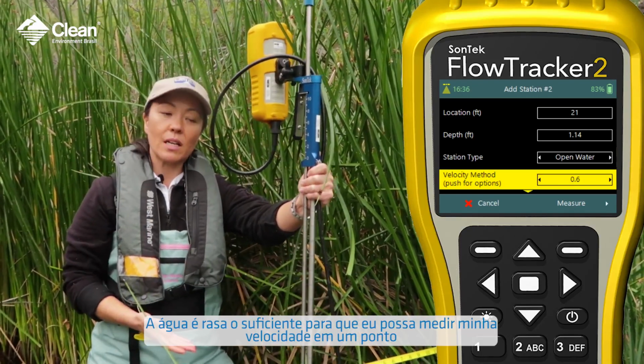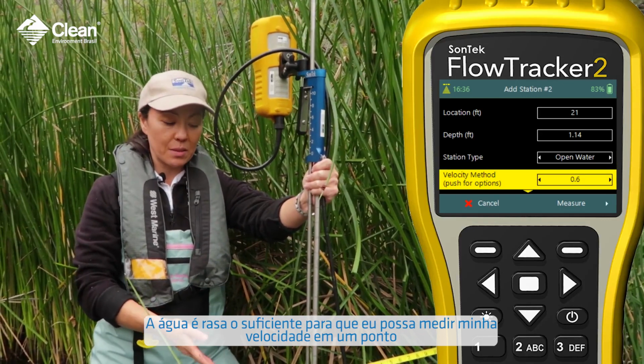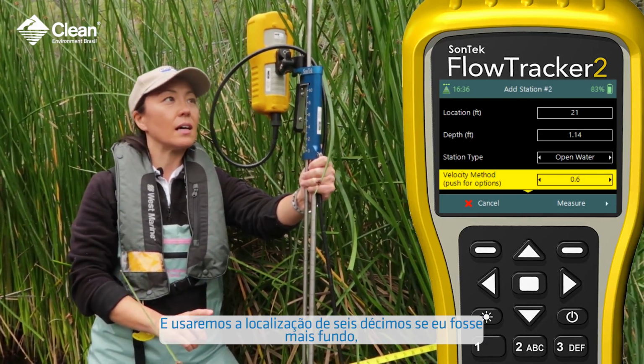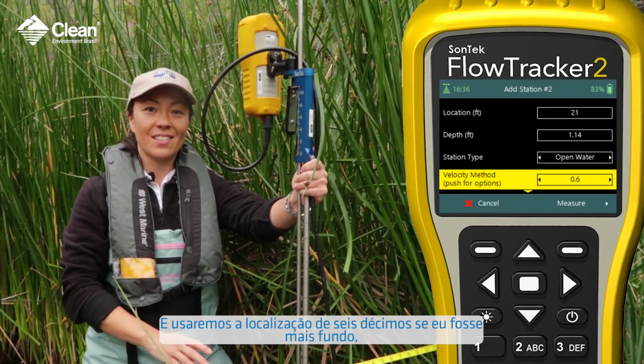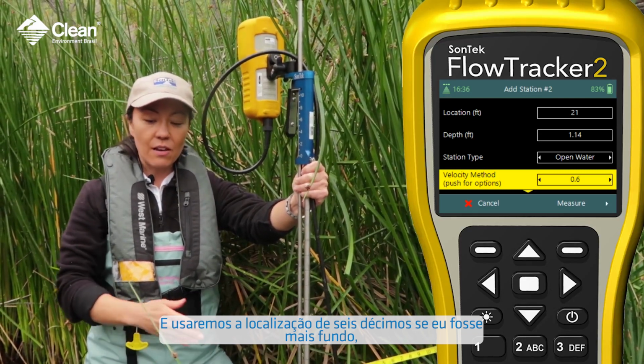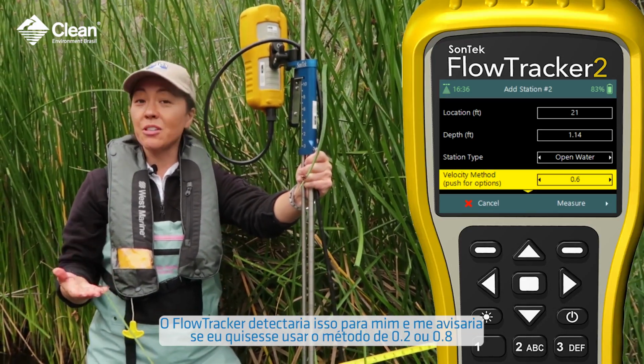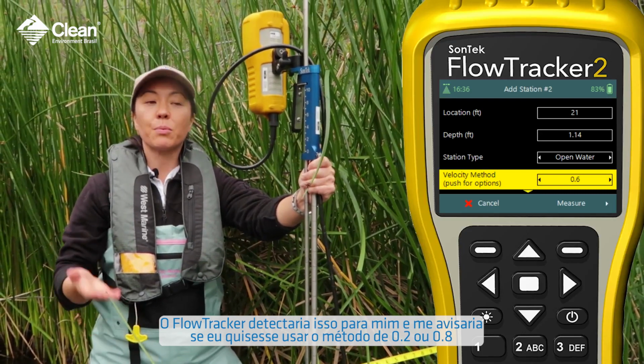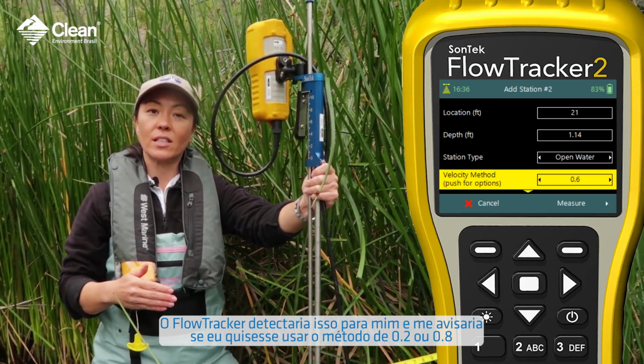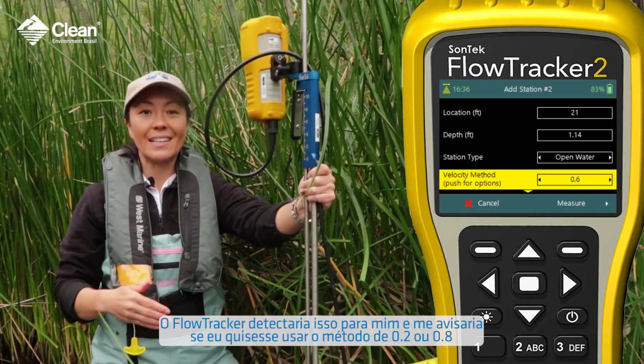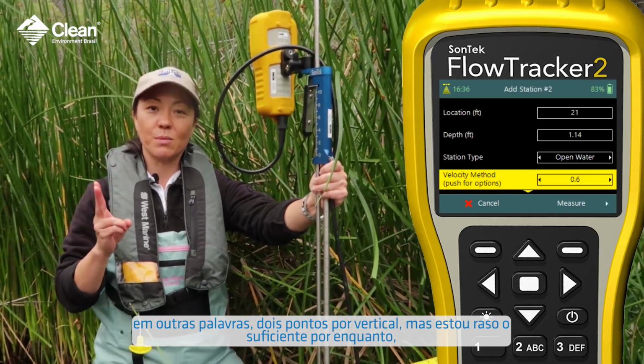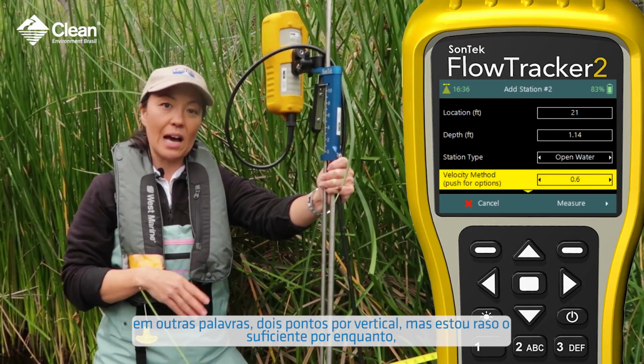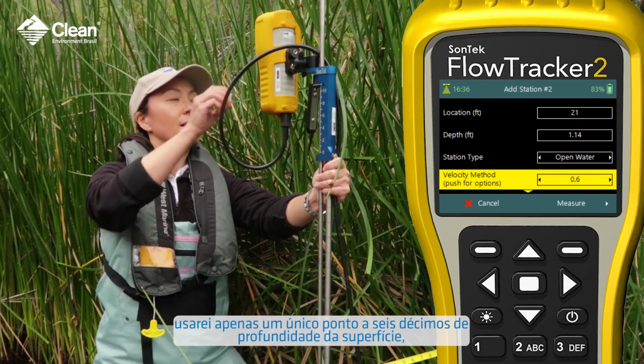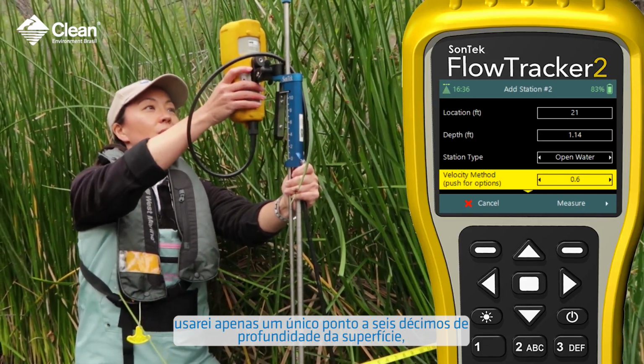The water is shallow enough so I can take my velocity measurement in 1 point, and we'll use the 6/10 location. If I were deeper, the FlowTracker would actually detect that for me and prompt me if I wanted to use a 0.2 or a 0.8 method, in other words 2 points per vertical. But I'm shallow enough for now. I'll just use a single point at 6/10 depth from the surface.